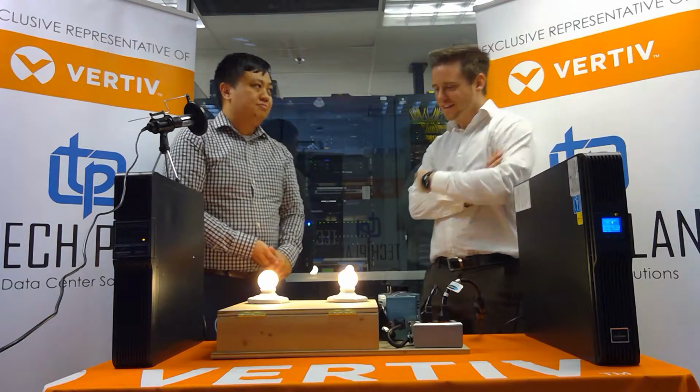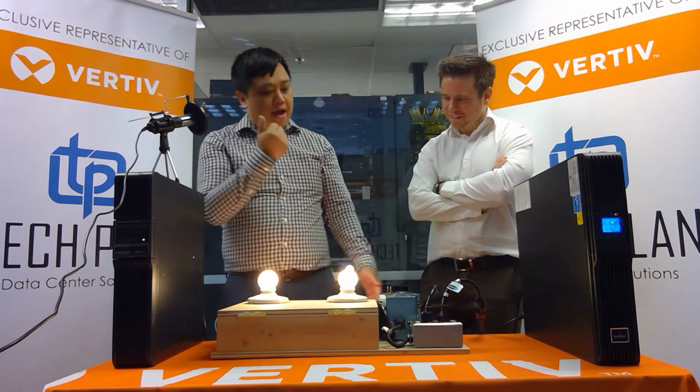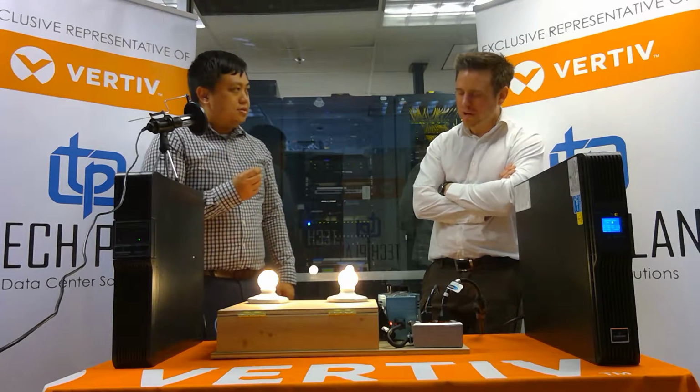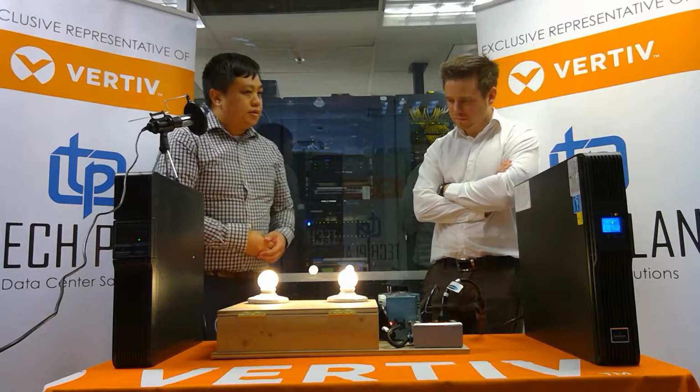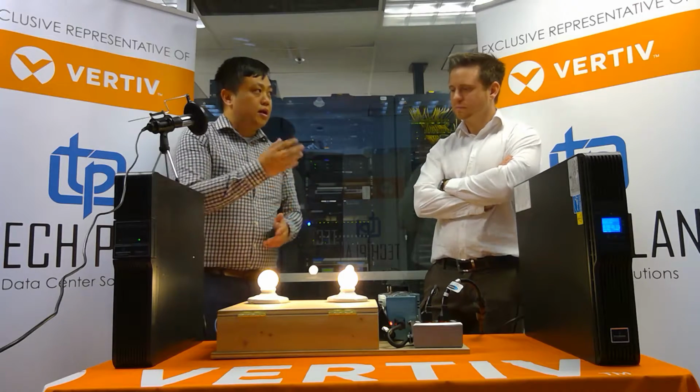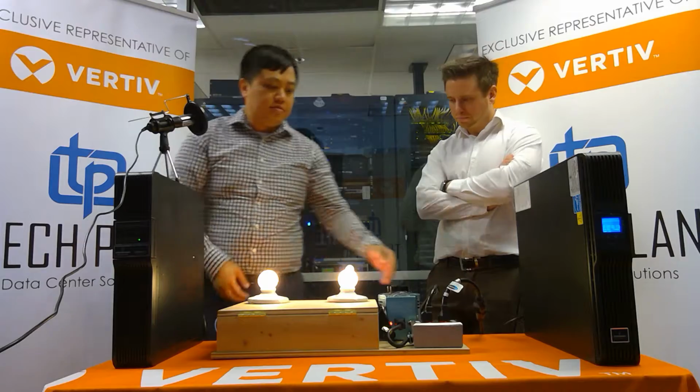You're too fast for me, Dennis. Can I see that again? Yeah, sure. So let's go back. Power comes back online. Another flicker there. And then still rock solid there. So they're qualifying the source. Back on. Let's go ahead and hit it again. Another power outage.